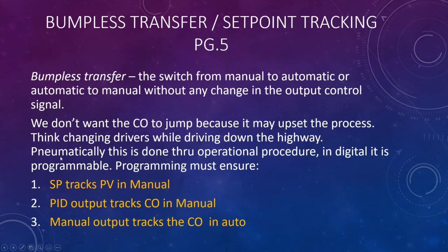In a digital controller, it is programmable. And the programming that we do to make sure that we get bumpless transfer has to do with what we are tracking, and we call it set point tracking. Okay, so the first thing that has to happen for bumpless transfer is that the set point tracks the process variable in manual.